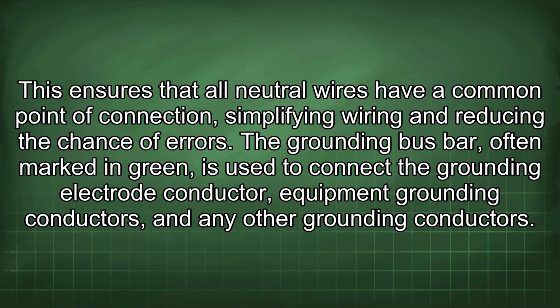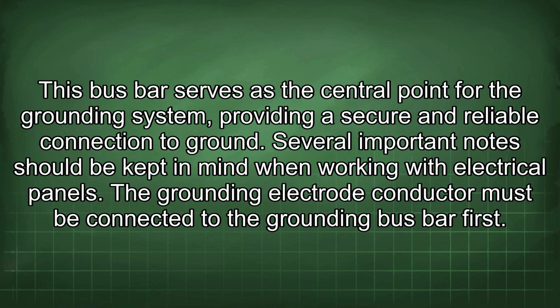The grounding bus bar, often marked in green, is used to connect the grounding electrode conductor, equipment grounding conductors, and any other grounding conductors. This bus bar serves as the central point for the grounding system, providing a secure and reliable connection to ground. Several important notes should be kept in mind when working with electrical panels.